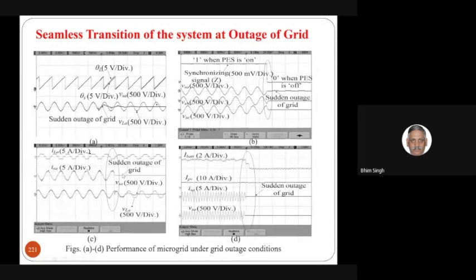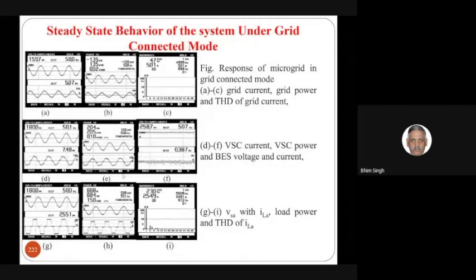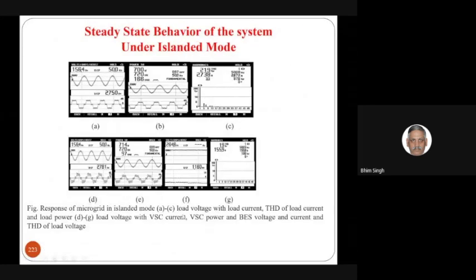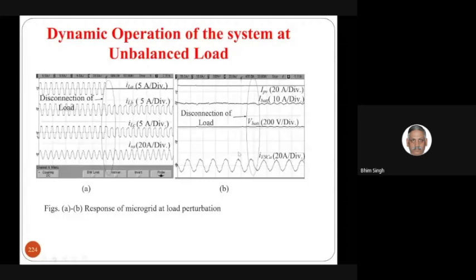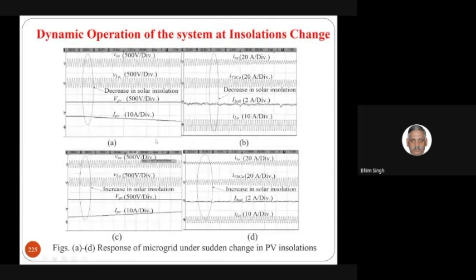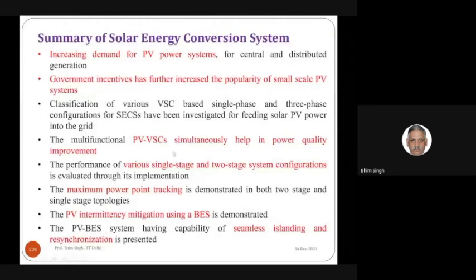And when the grid disappears, then it starts, and you are able to operate satisfactorily in the grid connected mode with less than 5% THD of the grid current, and the load current THD was quite high, 23%. And when you are operating in islanding mode or standalone mode, the load current THD is 29.7%, but the voltage THD is hardly more than 2%, 1.9%. And then how the load changes, the load gets unbalanced. Of course, grid current increases because now the power consumed by the load is less. Similarly, when the solar insolation changes, it works very well.